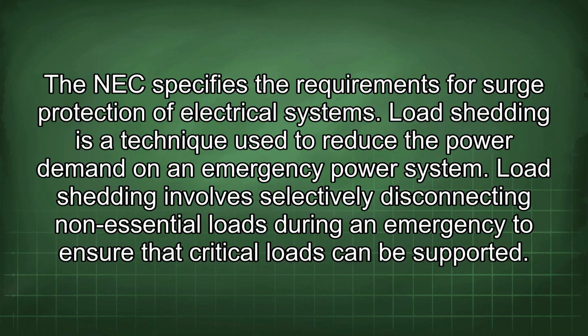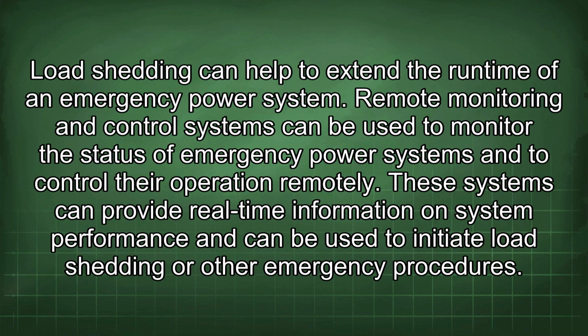Load shedding is a technique used to reduce the power demand on an emergency power system. Load shedding involves selectively disconnecting non-essential loads during an emergency to ensure that critical loads can be supported. Load shedding can help to extend the runtime of an emergency power system. Remote monitoring and control systems can be used to monitor the status of emergency power systems and to control their operation remotely.